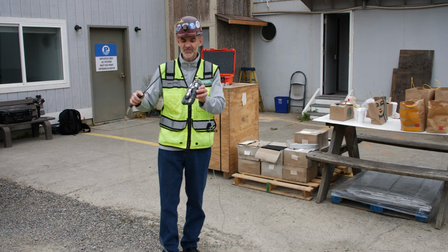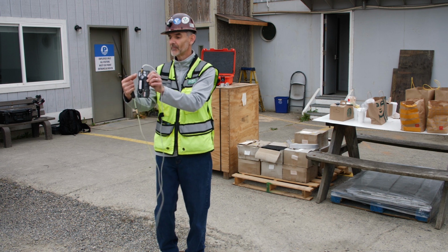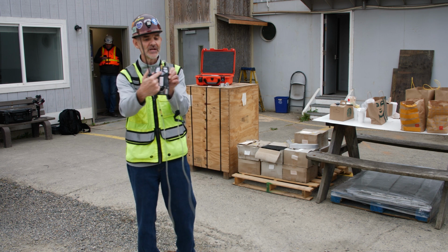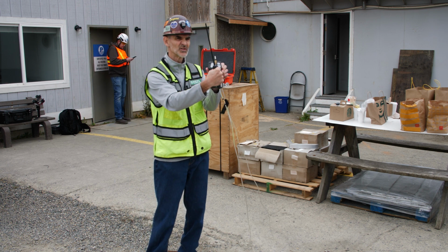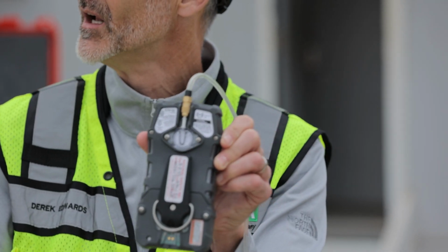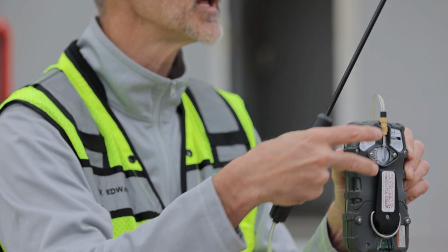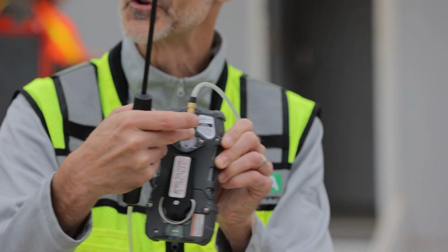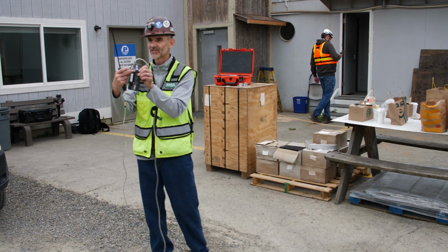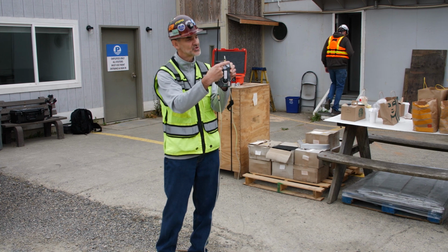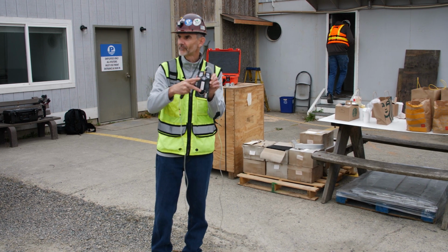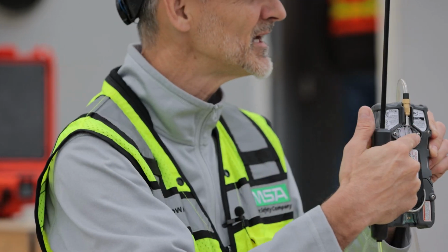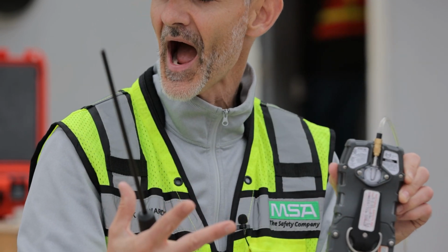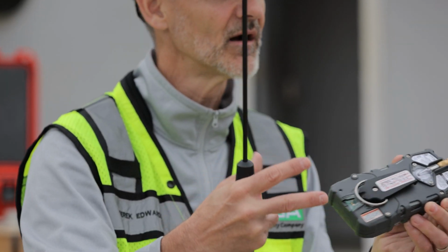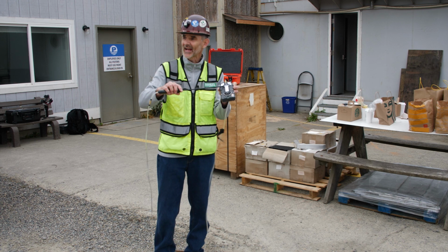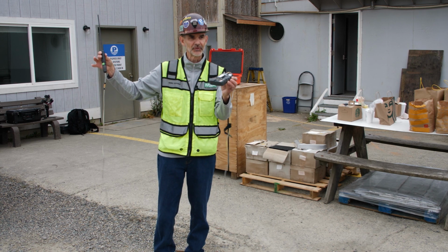Additionally, on the back of the instrument here, probably can't see it, but there is a secondary filter underneath that inlet right here. It's a little white filter about the size of a nickel. Over time, that can get dirty. It's replaceable. But if you see water droplets, this is a clear housing so you can see it. See water in there, 2 screws here, open it up, just let it air out. You may or may not need to replace the filter. Let it dry out, put the 2 screws back in there, and you'll be good to go. But that would be a secondary filter, and this is our primary filter.